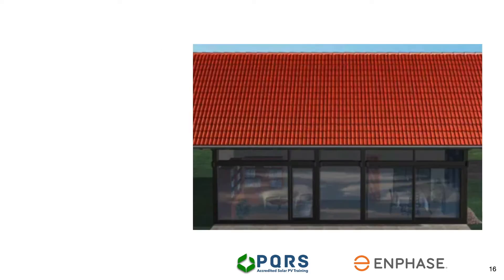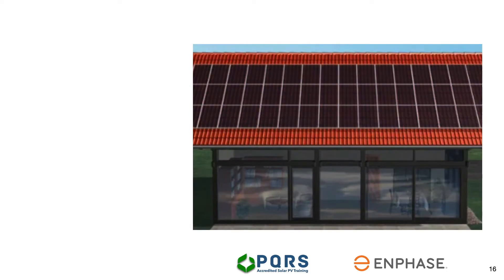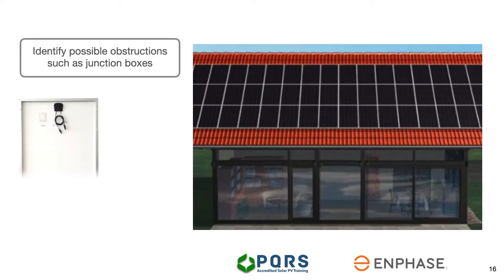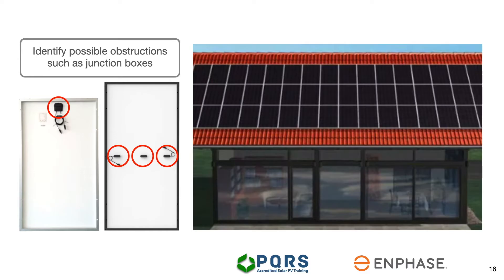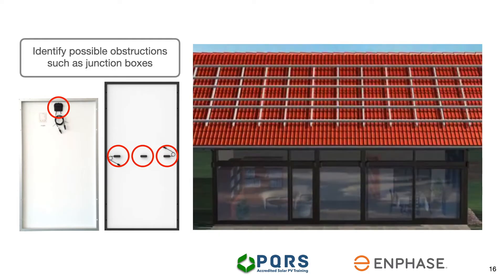Start with the design of your system by looking at the layout of the modules on the roof. Next, look at the modules and identify where the junction boxes will be positioned once installed. In some cases, junction boxes could cause obstructions and microinverters should ideally not be installed directly underneath them. Mark the position of each module on the mounting structure.